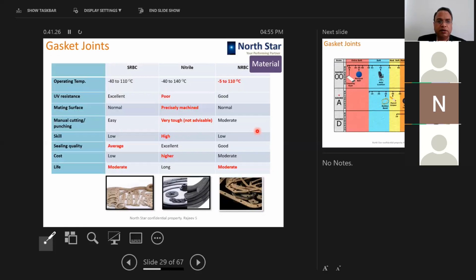Now coming to material, we can use three types of gaskets in a transformer. Nitrile, people say, is the best type of material available, but it has got its own problem. The red entries or red values are an indication of the negative aspect of this material, and most of the reds are in nitrile. The biggest problem with nitrile is that it has got very poor UV resistance.